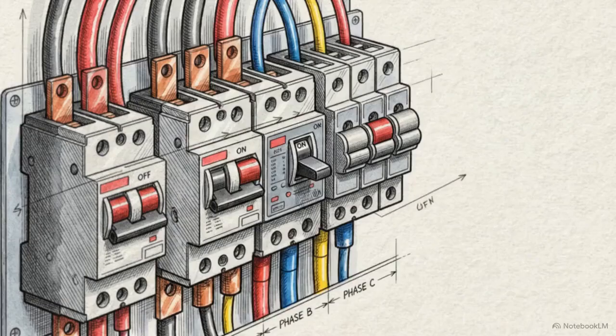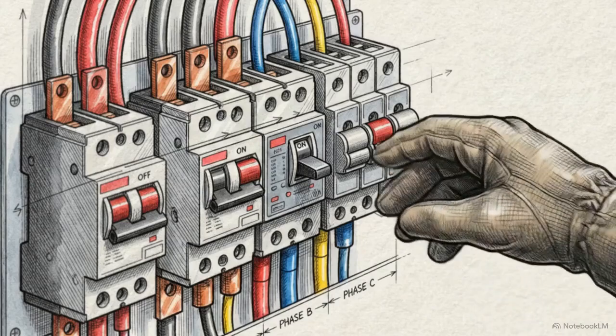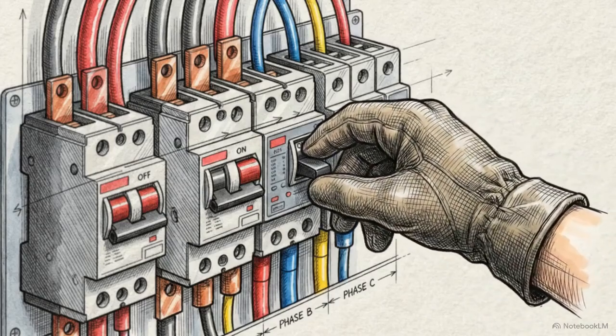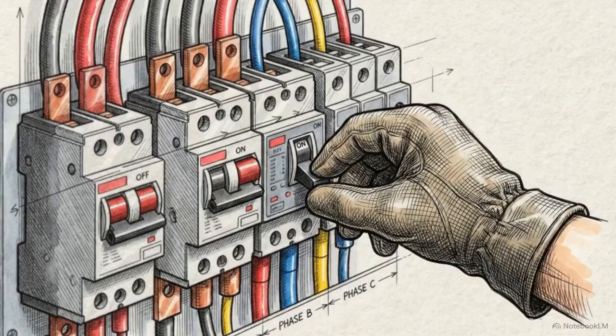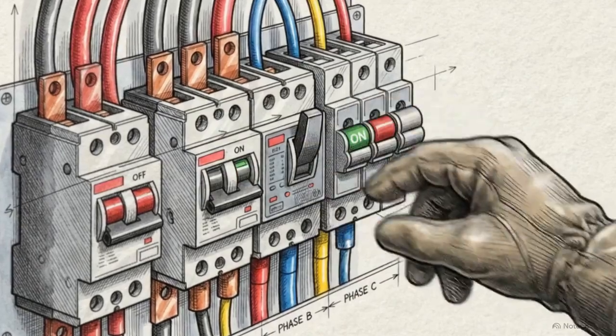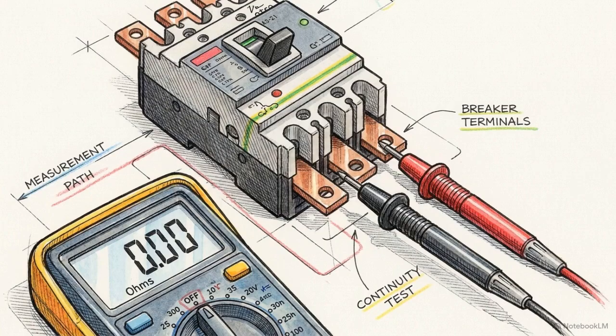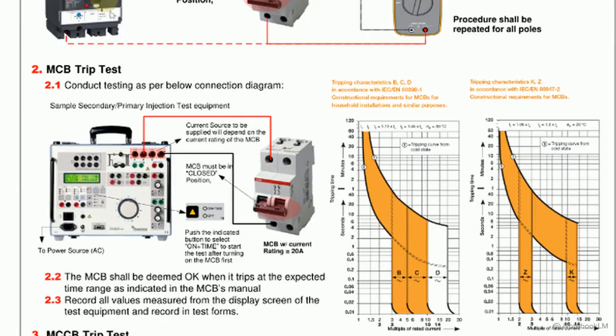The testing sequence begins with a mechanical inspection of the breakers. Engineers verify equipment labels, check torque marks on terminals, inspect arc chutes, and prove pole-to-pole continuity to confirm the physical hardware is intact. To test miniature circuit breakers, a secondary injection setup connects directly to the terminals to record the exact millisecond each pole trips.